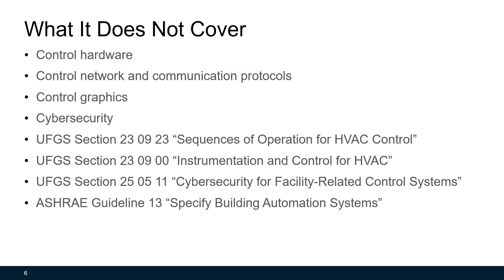Guideline 36 only contains control sequences, not full control system specifications. It won't cover control hardware specification, control network and communication protocols requirements, and it does not have requirements for control graphics or cybersecurity. For DOD managers, you can reference Unified Facility Guide Specifications Section 23 09 23, Section 23 09 00, or Section 25 05 11 for cybersecurity for facility-related control systems. For others, ASHRAE Guideline 13 on building automation systems has good information.